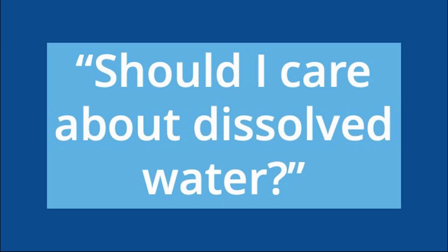All right, so on that note, we hear this often. People say, well, I don't care about dissolved water. Should we care about dissolved water? Well, it depends on what you're looking at. Are you likely to wipe a bearing with dissolved water? No. But are you going to cause metal to start deteriorating, have rust start showing up in bearings and causing problems? Yeah. But you're also moving the conversation from talking about equipment to the life of the oil.